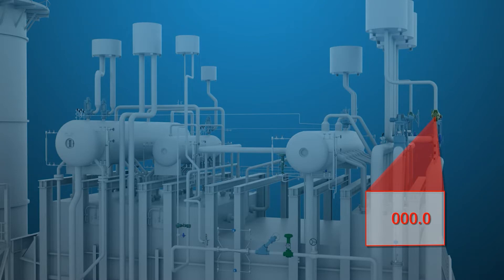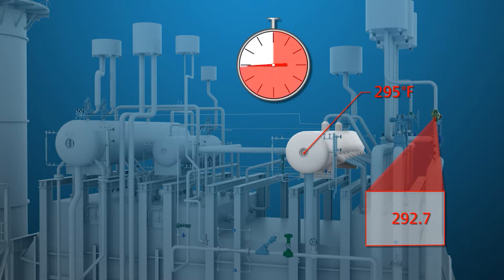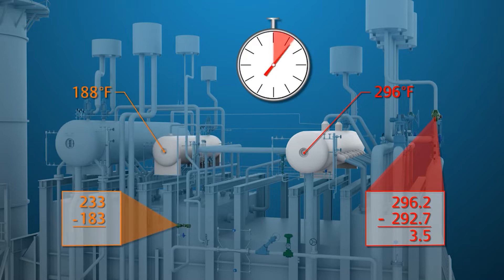Skyvent logic is programmed to observe the temperature change in the associated steam drum and limit the rate of change anywhere from 3.5 degrees Fahrenheit per minute in high-pressure steam to 50 degrees Fahrenheit per minute in the IP and LP steam drums.